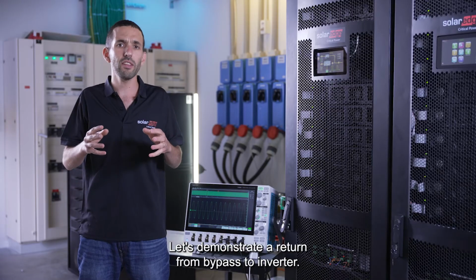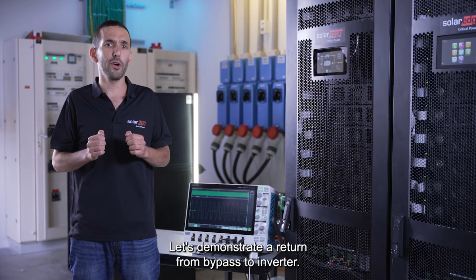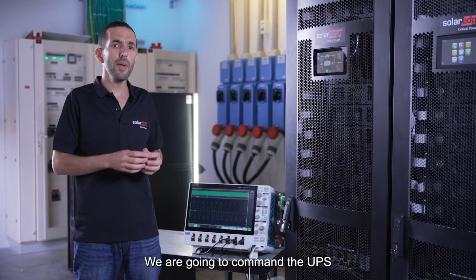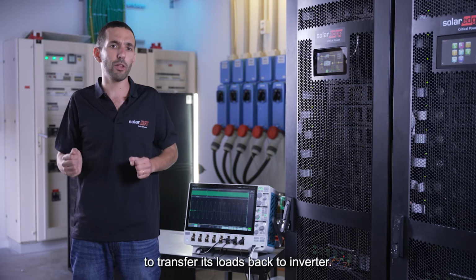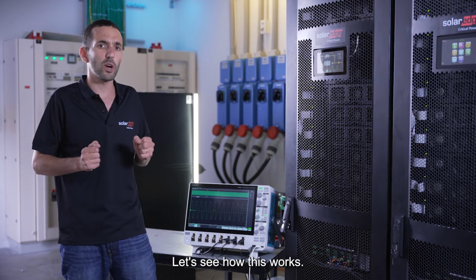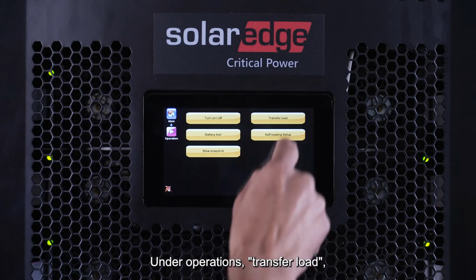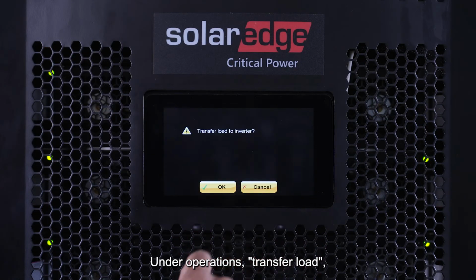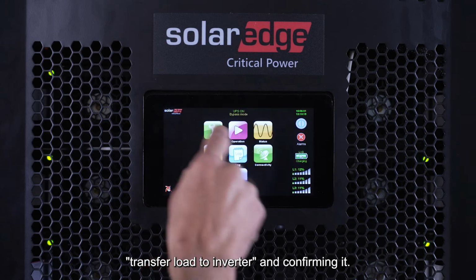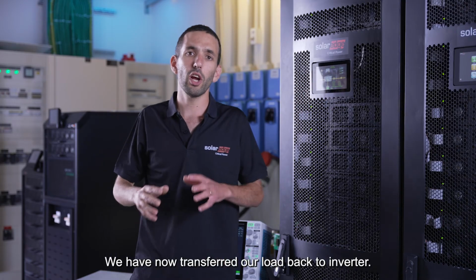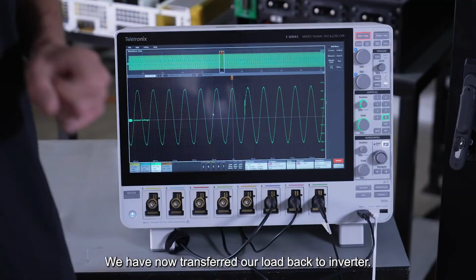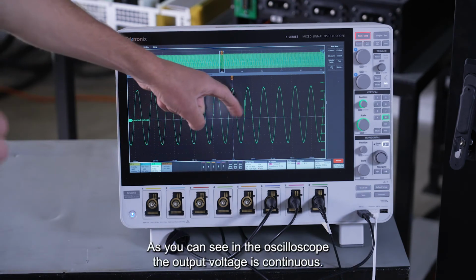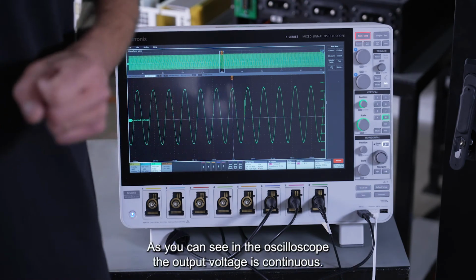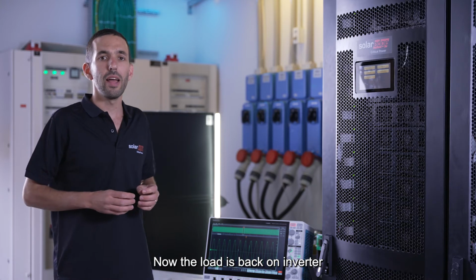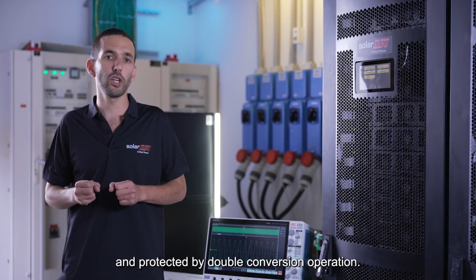Let's demonstrate a return from bypass to inverter. We're going to command the UPS to transfer its loads back to inverter. Let's see how this works. Under Operations, Transfer Load to Inverter, and confirming it, we have now transferred our load back to inverter. As you can see in the oscilloscope, the output voltage is continuous. Now the load is back on inverter and protected by double conversion operation.